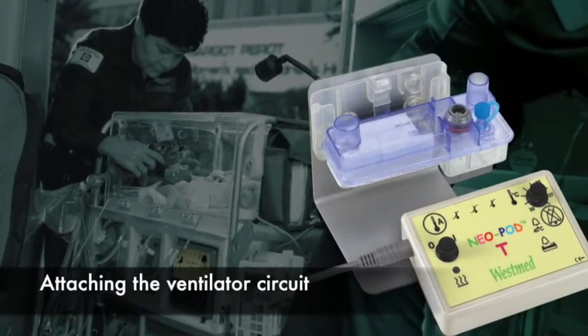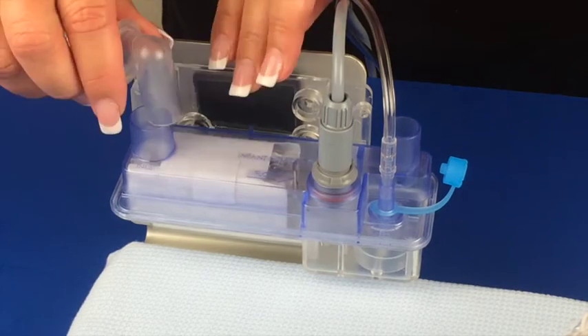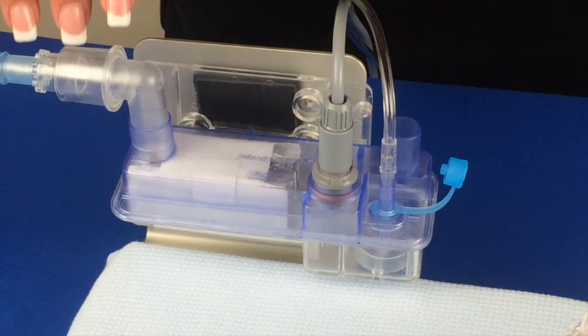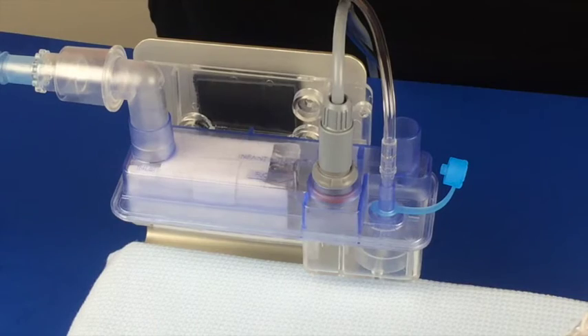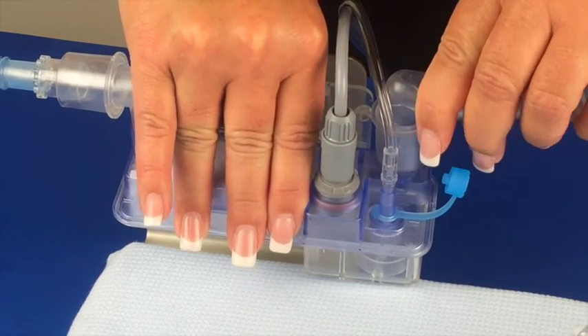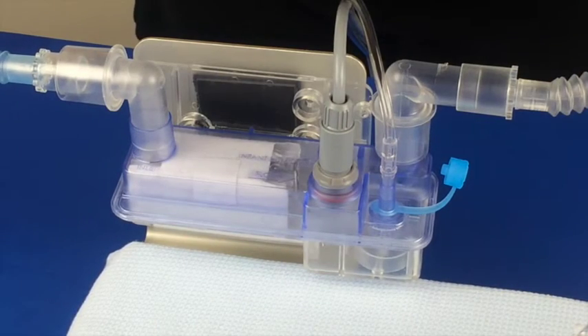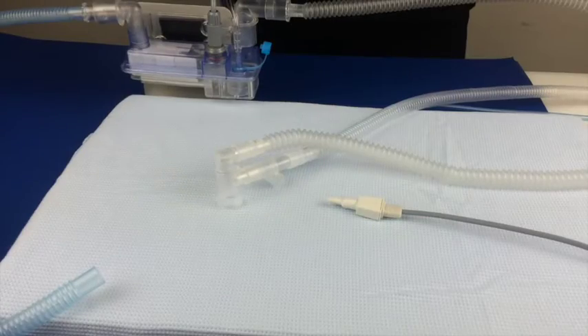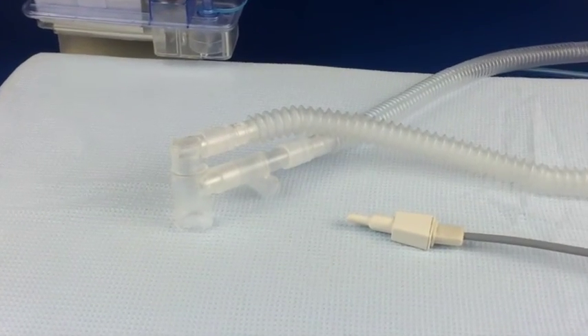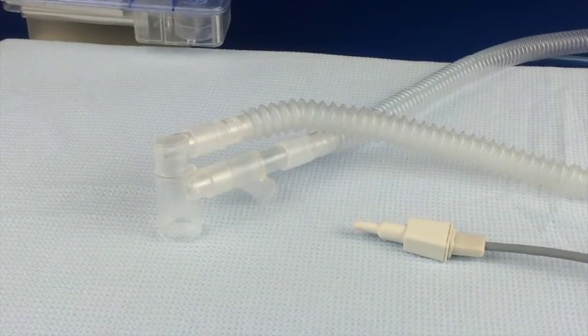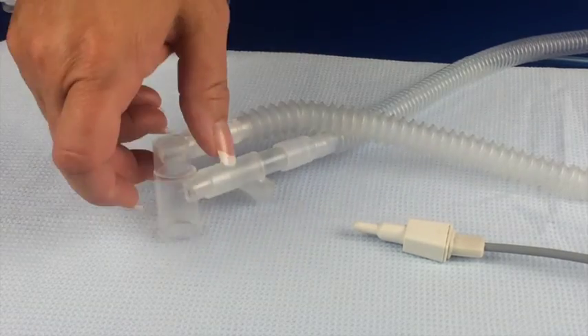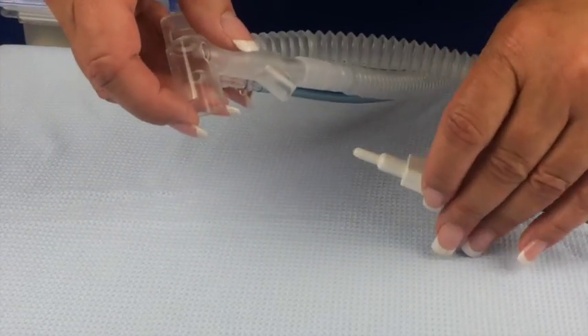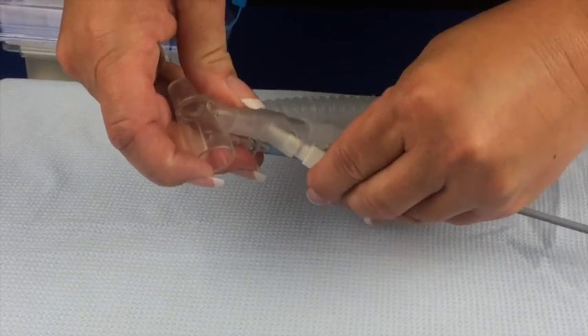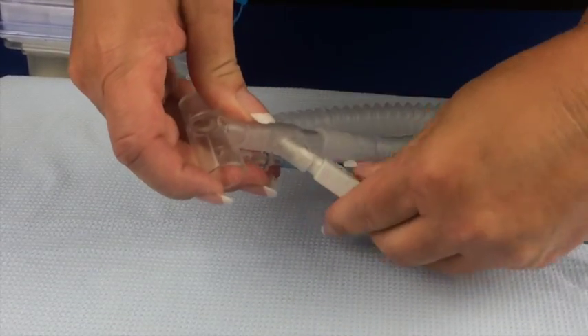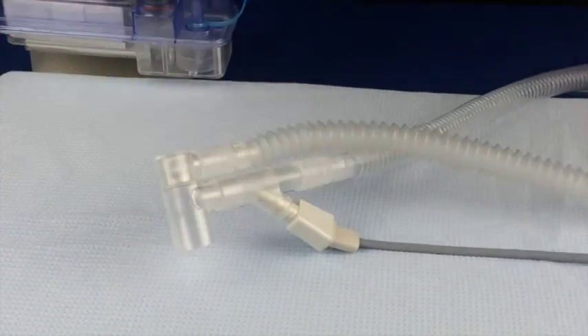Attaching the ventilator circuit to Neo-Pod. Attach the inspiratory limb from the ventilator to the inlet port of the Neo-Pod. Next, connect the patient inspiratory limb to the Neo-Pod. The end with the Y adapter connects to the patient. Connect the temperature sensor probe to the patient Y. This is the cable with the white-tipped probe. Connect this probe to the temperature monitoring port of the circuit at the patient airway.